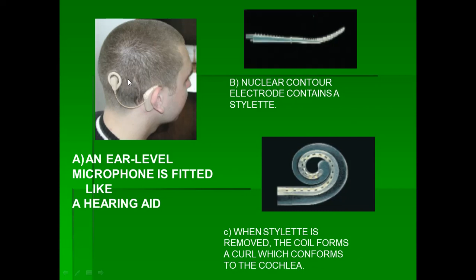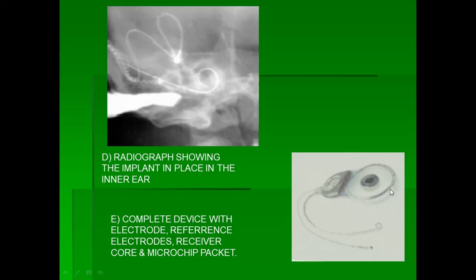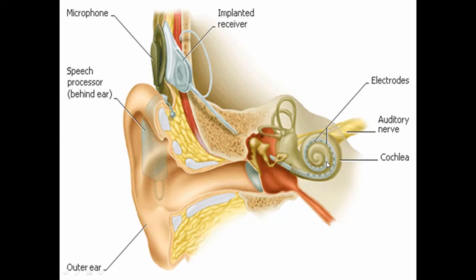Here is the electrode array, which is inserted into the cochlea and can be seen through a radiograph. The internal component comprising the receiver and the electrode array enters into the cochlea. You can see the microphone and speech processor. The speech processor can be at the level of the ear, or it can be a body-worn type of speech processor. The signals from here are transmitted to the transmitter. Here it is labeled as microphone, but this is not the microphone, this is the transmitter. The transmitter sends the signal to the receiver, which is deep to the skin and subcutaneous tissue on the bone. And from this, the signals are transmitted to the electrode array, which is directly present in the cochlea and which stimulates the cochlear nerve.